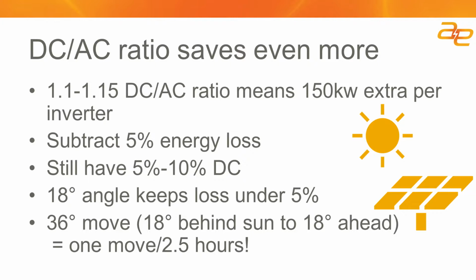So an 18-degree move, or 18 degrees off of ideal, is a 95% DC output from the modules. So if you were to be 18 degrees behind the sun, you'd have 95% of rated output, and that would still be within the DC-AC ratio losses from the site. So now we could actually do a 36-degree move from 18 degrees behind the sun to 18 degrees ahead of the sun and get full output from your inverter throughout that entire time period. And that translates to 1 move every 2.5 hours.